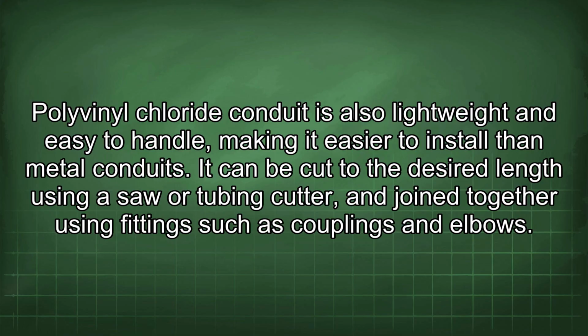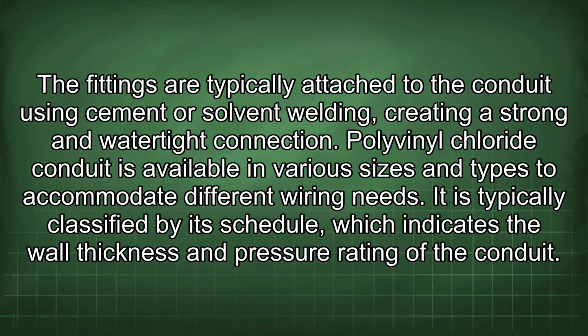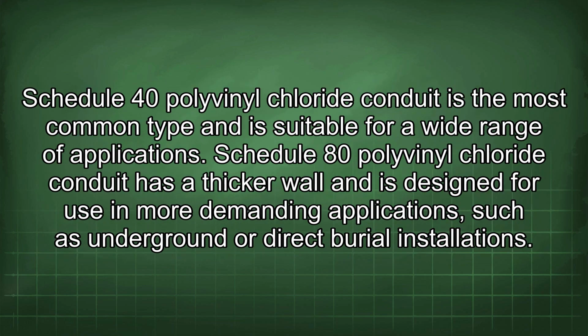It can be cut to the desired length using a saw or tubing cutter, and joined together using fittings such as couplings and elbows. The fittings are typically attached to the conduit using cement or solvent welding, creating a strong and watertight connection. Polyvinyl chloride conduit is available in various sizes and types to accommodate different wiring needs. It is typically classified by its schedule, which indicates the wall thickness and pressure rating of the conduit. Schedule 40 polyvinyl chloride conduit is the most common type and is suitable for a wide range of applications.